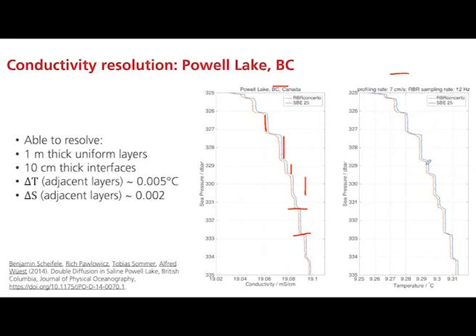And so you can see in temperature we resolve these steps very well. By the way, the reference here was a Seabird 25, or the other instrument here is a Seabird 25 at 4 hertz. We sampled at 12 hertz. And then conductivity is on the left panel here, and you can see that we've done just as well of a job characterizing these steps. And I find this really interesting because we have a cell that has an effective sampling radius of, it's sensitive to changes on the scale of 15 centimeters, but it's very easily measuring these interfaces, which are thinner than 10 centimeters. And I think that really reflects the fact that, again, the bulk of the measurement occurs within this conductivity cell itself.